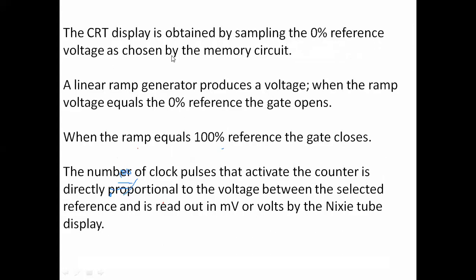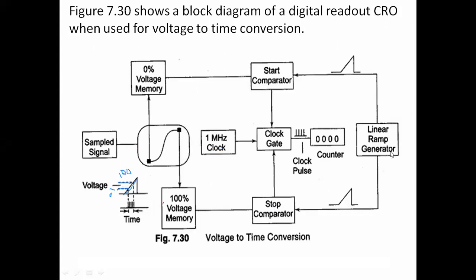The linear ramp generator produces the voltage. When the ramp voltage equals the 0% reference, the gate opens. The start comparator produces a signal that opens the clock gate, and the 1 MHz clock pulses pass through and are counted by the counter. Next, when the ramp voltage equals the 100% voltage — the maximum position for our sample time — that voltage is sent to the stop comparator. When these two are equal, the stop comparator produces the stop signal, closing the clock gate.